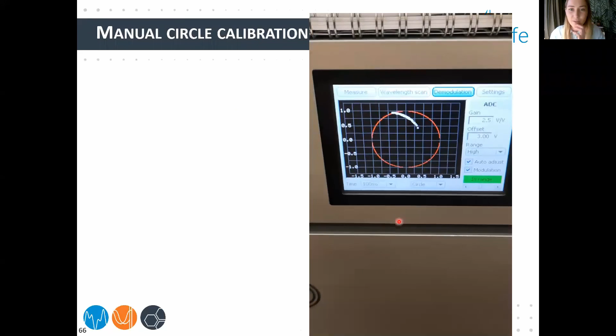And then a few more tricks that I have. If during the experiments the signal went out because of the drift or something else, what you can do is manually tap on the system until you have one circle of noise, and then in here choose calibrate, and then continue tapping. So you're inducing one circle of noise. You continue that while it's in progress, and you see as a result, you have a signal back.